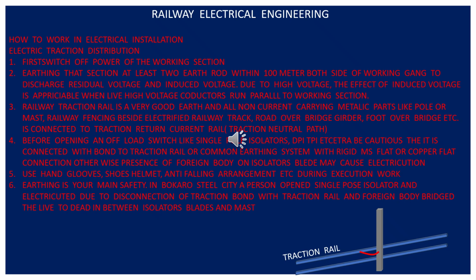Another thing is contractors erecting masts beside the railway track without informing any authority and without any permit to work. It is not acceptable, and they must be punished if any mishap occurs. If they had connected the bottom portion of the mast with the traction rail, our circuit breaker would trip, though the wire may be snapped, but they would be safe. It is a mistake, I can't say it is a crime. Take a permit to work from the proper authority, then you do all these things.